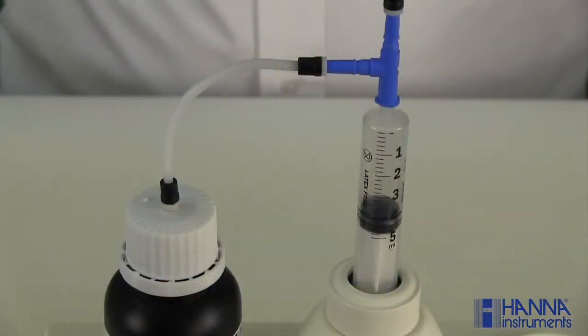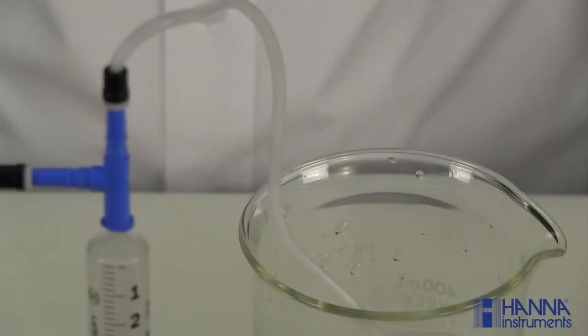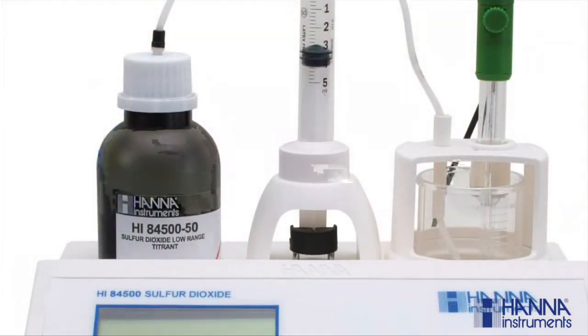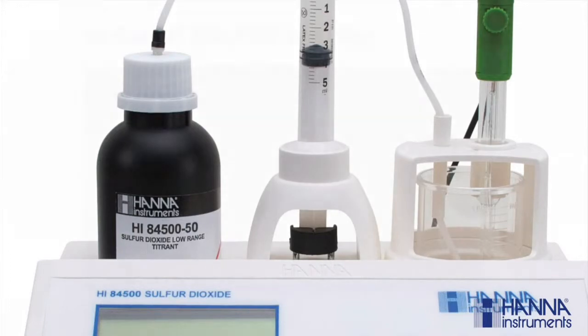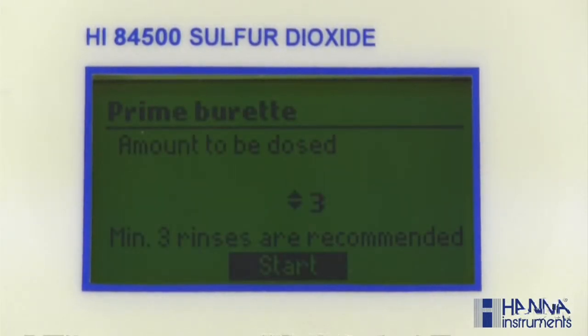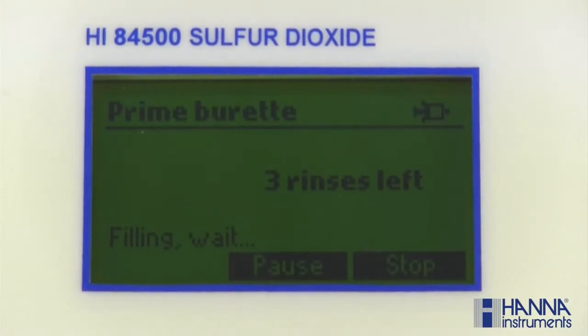You should always run a prime cycle if you notice that there is no titrant in the dosing tip, whenever the dosing system tubes are replaced, whenever a new bottle of titrant is used, before starting a series of titrations, or in this case, before starting a pump calibration. Make sure the aspiration tube is inserted into the titrant bottle and the dosing tip is placed into a rinse beaker. Double check you have the correct titrant. We're using the HI-84500-50 low range titrant. Select the prime option from the titration mode. Adjust the number of rinses with the arrow keys and press start. The number of syringe rinses can be set between 1 and 5.